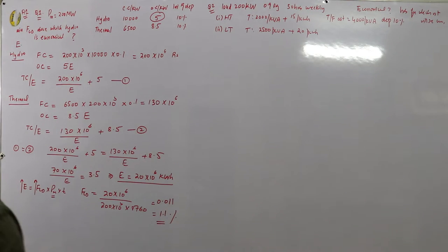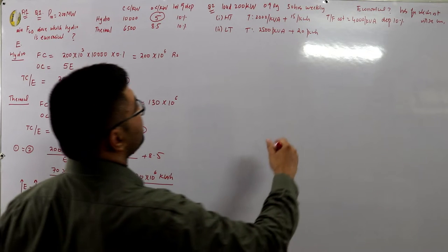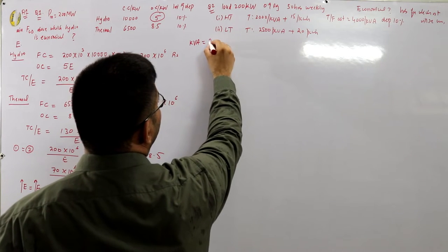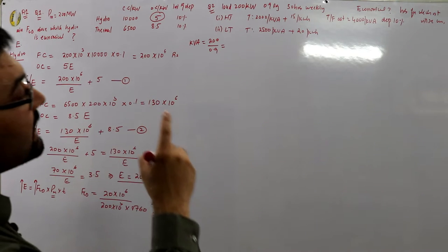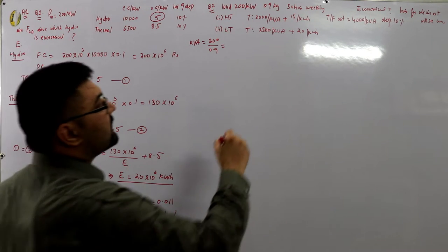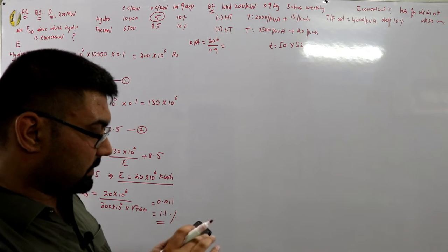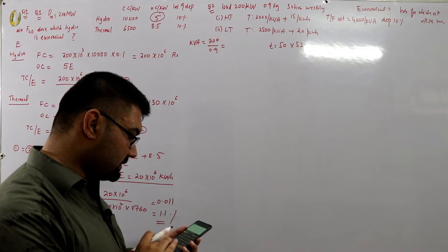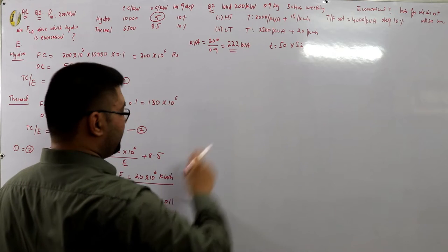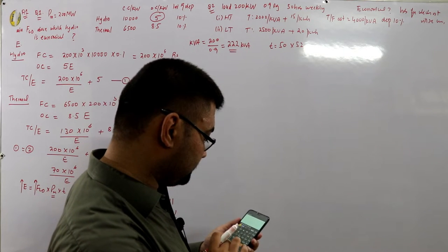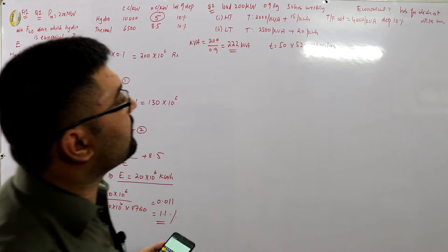First, we need to find the KVAs: KVA = kilowatt / power factor = 200 / 0.9 = 222 KVA. The time is 50 hours per week, so yearly hours = 50 × 52 = 2,600 hours per year. These are the hours of operation for which we'll calculate costs.